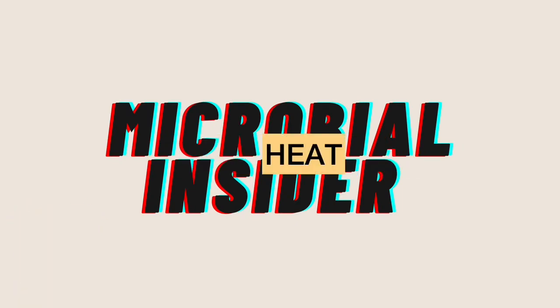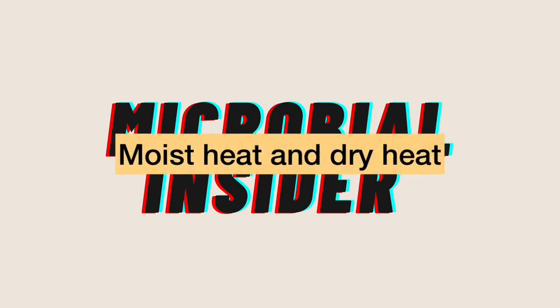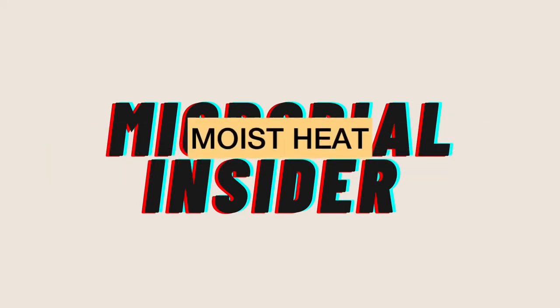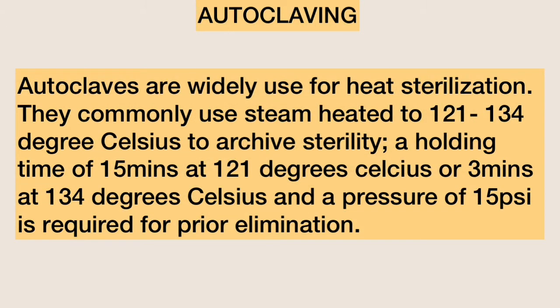The first physical method we will be talking about is heat, which can be further divided into moist heat and dry heat. Methods that employ moist heat include autoclaves, which are widely used for heat sterilization. Steam is commonly heated to a temperature of 121 to 134 degrees Celsius. A holding time of 15 minutes at 121 degrees Celsius, or 3 minutes at 134 degrees Celsius, and a pressure of 15 psi is required for sterilization.